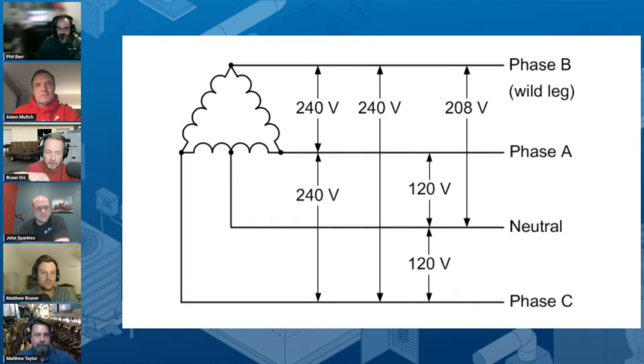Looking carefully at phase monitoring — making sure you have some sort of phase monitoring in place with any mission-critical components. I used to install phase monitors on rooftop units doing bank work — basic Y-configured three-phase systems that wouldn't come with any phase monitoring from the factory. We would always install those — the ICM 450 — and they would often prevent significant failure from single phasing or voltage imbalance. Sometimes that stuff comes from the utility: the utility will drop a leg or you'll get voltage imbalance straight from the utility. That's another advantage of phase monitoring for something you cannot prevent.